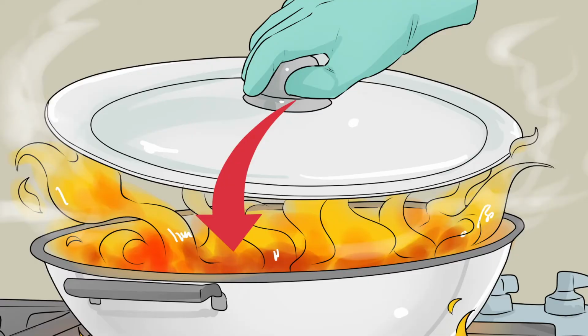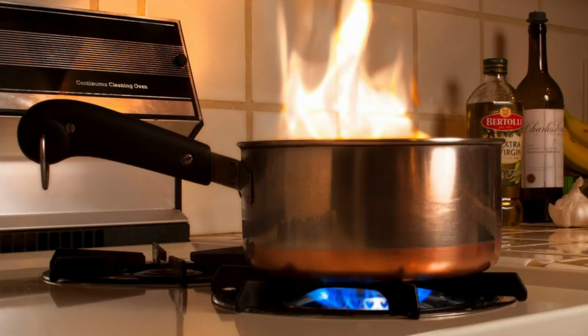Class F is the kitchen cooking oils, and basically they're extinguishers that are specifically designed for cooking oils and fats that are used when cooking, like the chip fryer oil and anything related to that. With Class F and the cooking oils, you must use the wet chemical fire extinguisher because it's specially designed for that. You cannot use foam, you cannot use water, and you cannot use dry powder. So you've got to be careful. Most kitchens will have a wet chemical fire extinguisher.